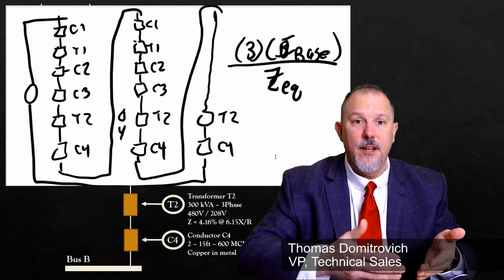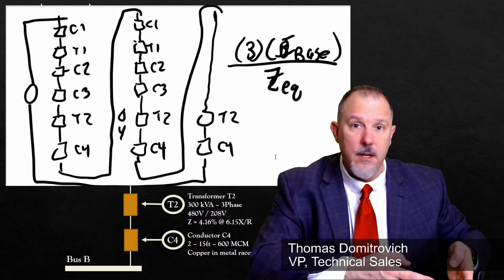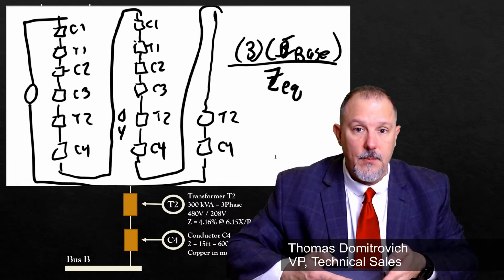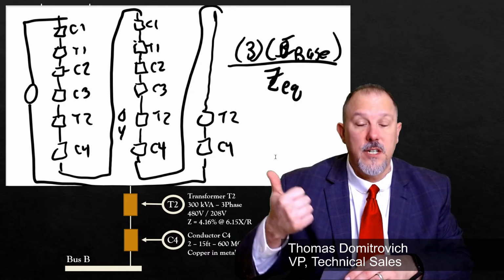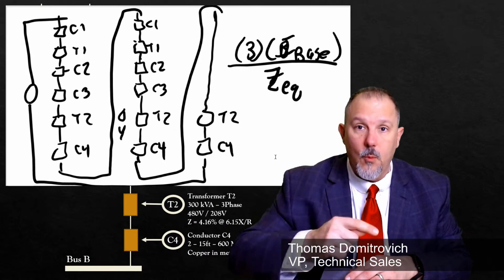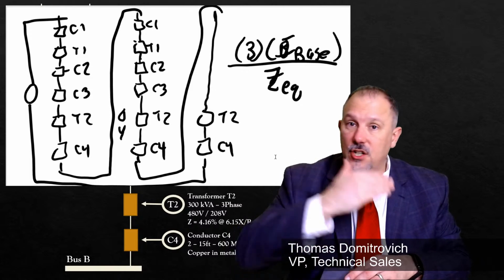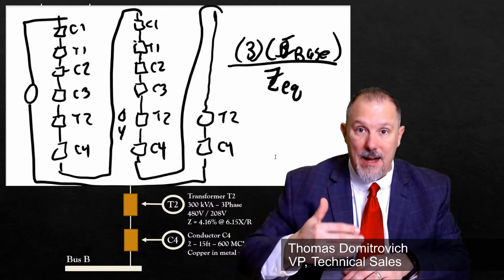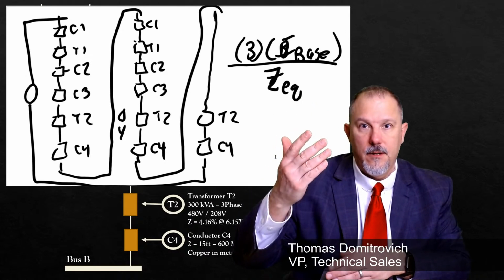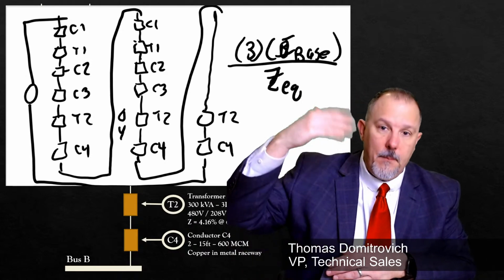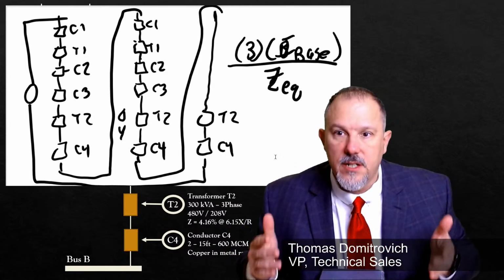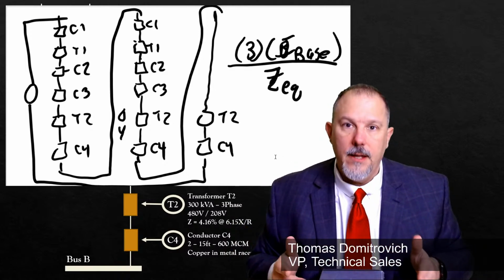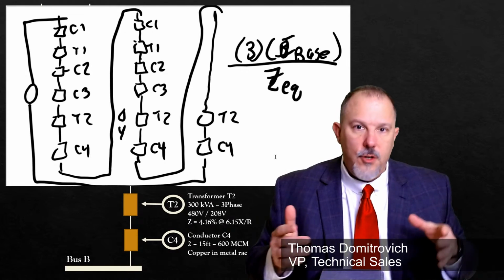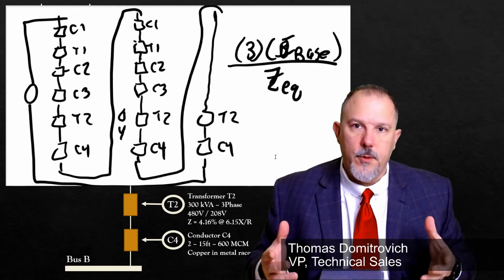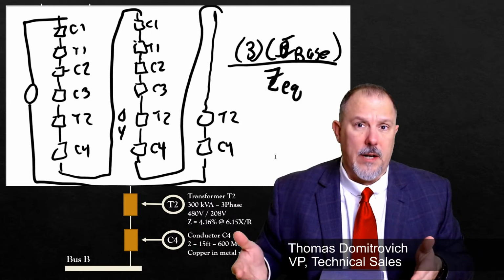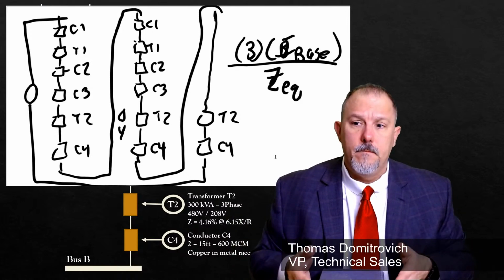You know how to create the positive sequence impedance, which means you know how to create the negative sequence impedance, and now you know how to make the zero sequence impedances and what to omit. Beware of your delta-Y grounds. That's your isolation. If it's a Y to Y, you include the other impedances upstream. Very rarely do you see a Y to Y transformer. The most common transformer you're going to come across in the power distribution system is a delta-Y ground. So that's how you do it.